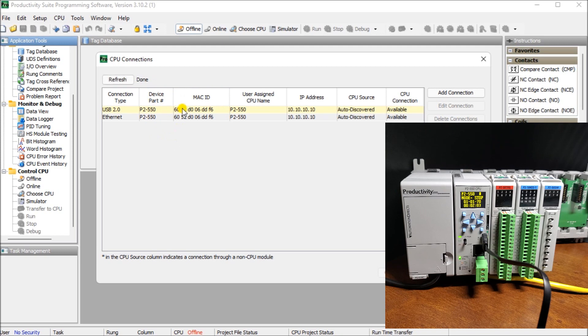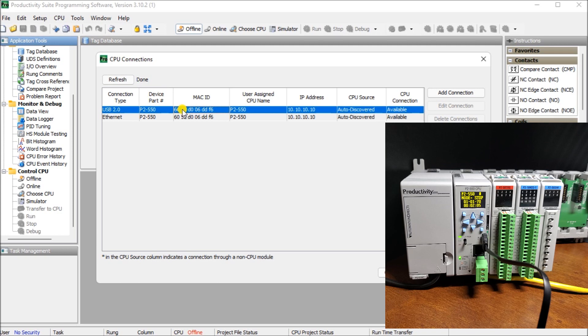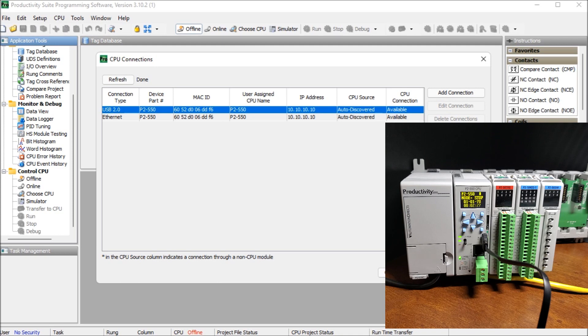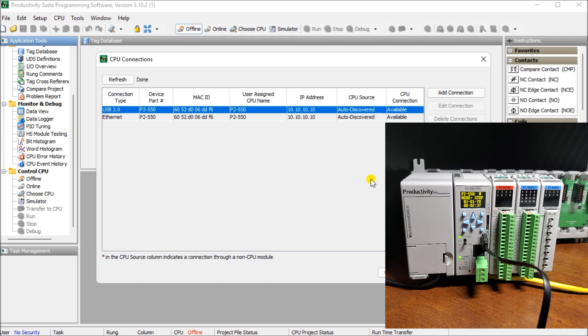So once I select the CPU one, you can see that my selection on the right hand side here under my CPU connections window will now change. So right now I'm communicating my USB 2.0 and I can say blink the CPU display. And when I do, you will see that that CPU display now starts blinking indicating that I have communications from my USB to the controller itself. And we can hit stop. And that will stop that blinking. So we know that that communication is good.